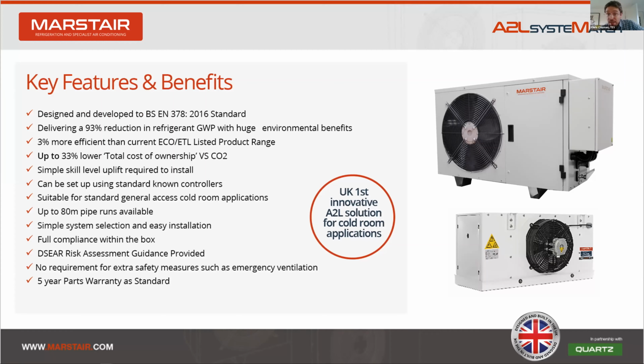To summarise the key benefits then, this is a simple skill uplift for contractors. It will be very similar to what they already know. We just recommend installers complete a short course on the use of flammable refrigerants, whereas alternative solutions such as CO2 require a much greater uplift in terms of skills, training, and equipment as well. The contractor on these systems can continue to use the controls they're familiar with. The wiring is very, very similar. System selection will be simple, as can be seen from the table we showed previously, in terms of using your room size, the capacity, pipe run, and refrigerant charge. There are massive environmental benefits in terms of improved energy efficiency and huge reductions in refrigerant GWP per system.